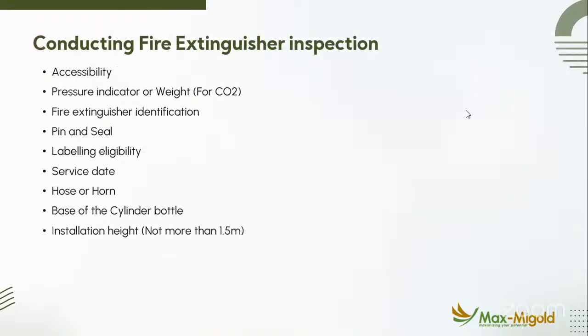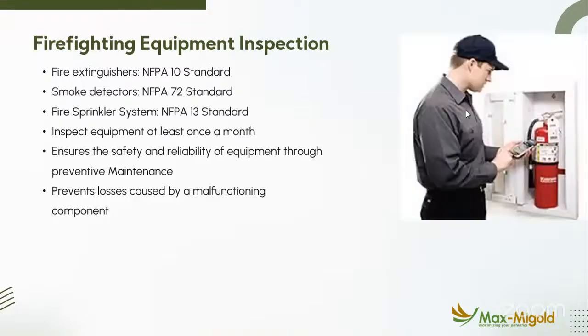One, fire extinguishers follow a standard called NFPA 10, National Fire Protection Association Standard 10. The smoke detector, which is the alarming and signaling system, NFPA 72, needs to be followed. The fire sprinkler system, NFPA 13, National Fire Protection Association Standard 13, needs to be followed. If you have a fire pump house, meaning that you have hydrant pumps within your facility, you have fire engine and what have you, that follows NFPA 25, both for the design and maintenance. National Fire Protection Association, US Standard 25.